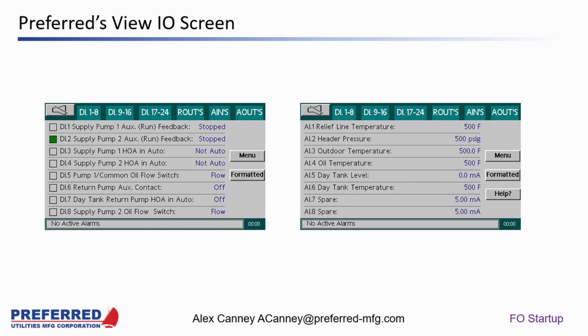Is that something that you use a lot when starting up and troubleshooting? I'm kind of old school about that. I like a wiring diagram with a meter, but since we have now gotten more into touchscreens and operator interface panels, the I/O screen is a very valuable tool to verify that, say, a flow switch is in a correct state, or that a leak switch is in a correct state, or the analog, what are you reading voltage wise? Is it showing you 20 milliamps if the tank's 100% full, but in actuality the tank's empty? That's a good quick reference point instead of having to go physically look, or you can do everything right there at the panel.